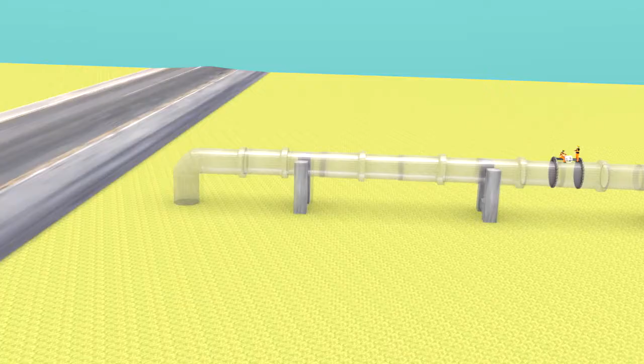On the day of the accident, the commissioning of the tie-in connection was completed at around 4 pm. The project team decided to go ahead with the opening of the tie-in connection. Unknown to the plant officials, hydrocarbon had leaked into the cooling water line during a previous incident and had accumulated in the pipeline. As soon as the valve was opened, these hydrocarbons trapped in the pipeline found an exit.